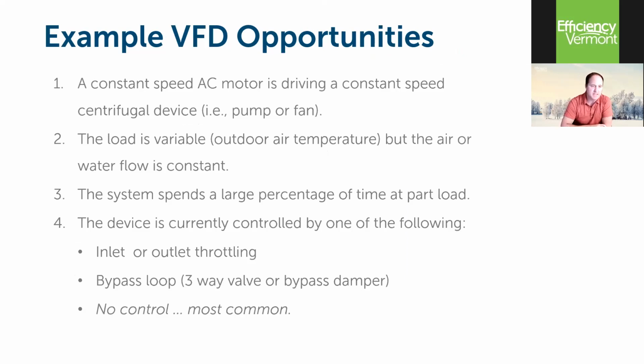Example VFD opportunities: constant speed AC motor driving a constant speed centrifugal device, pumps and fans, we've said it. The load is variable, outdoor air temperature, but the air or water flow is constant. System spends a large percentage of time at part load, which is pretty much by definition all HVAC equipment. HVAC equipment is sized for design days, hottest day of the summer, coldest day of the winter. That is, 10, maybe 20% of the hours in a year. So the rest of the year that we're heating and cooling, your systems are running at part load. And if your fans and pumps can only run at 60 Hertz, that's all you can deliver. You have no speed control to match pump and fan speed to the demands on the building. And that's where the VFDs really shine.